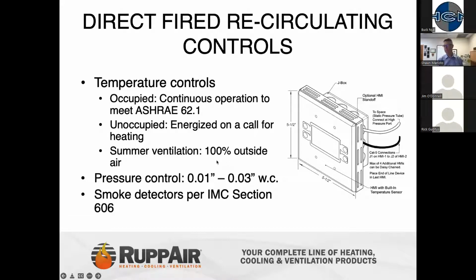Within this, make sure you have pressure controls that control the space pressure continuously, and make sure you incorporate things like smoke detectors, interfaced to the products as well, to be able to shut down a system in case of a fire.